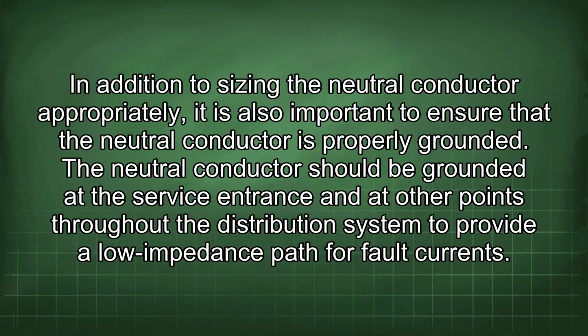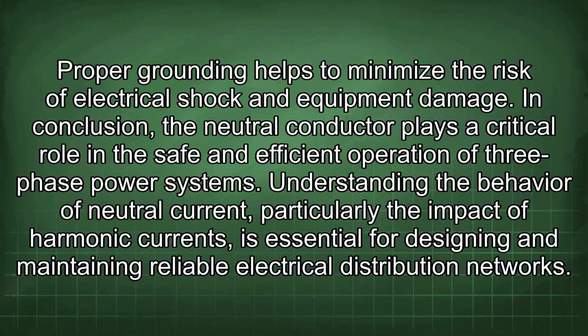In addition to sizing the neutral conductor appropriately, it is also important to ensure that the neutral conductor is properly grounded. The neutral conductor should be grounded at the service entrance and at other points throughout the distribution system to provide a low impedance path for fault currents. Proper grounding helps to minimize the risk of electrical shock and equipment damage.